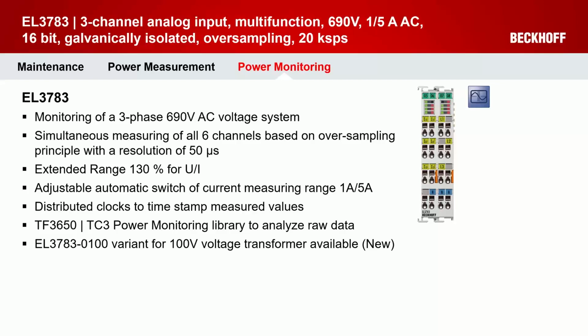For analyzing this raw data, we have implemented a power monitoring library, especially for these two terminals, to allow the customer an easy power quality analysis of the connected grid. Another variant we have implemented, because a lot of customers ask for a 100 volt voltage transformer terminal. So this variant is available now and allows measuring medium voltage grid connection points.